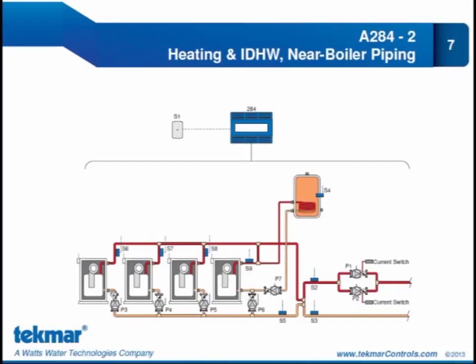So the way this will operate is all 4 boilers will provide space heating to the load, which we don't see pictured here in this diagram. But if there's a domestic hot water call, the 4th boiler will operate to provide water for the domestic hot water operation alone. So P6 will shut off and P7 will operate instead. We do have, again, our boiler inlet sensor S5, and we have individual boiler outlet sensors so that we can do our delta T monitoring.